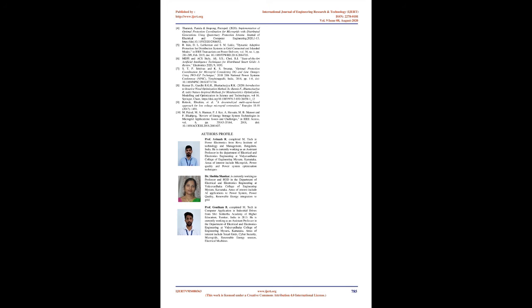microgrid central controller. In the decentralized multi-agent approach, the restoration action sequence of the microgrid after the fault is determined by the online data related to the power generated and the load consumption. To do this, the microgrid components such as micro sources, storage devices, and loads are dynamically modeled, and then using the distributed averaging method, a decentralized multi-agent based approach to restore the microgrid loads and generations with a proper sequence of actions after a total blackout is designed.